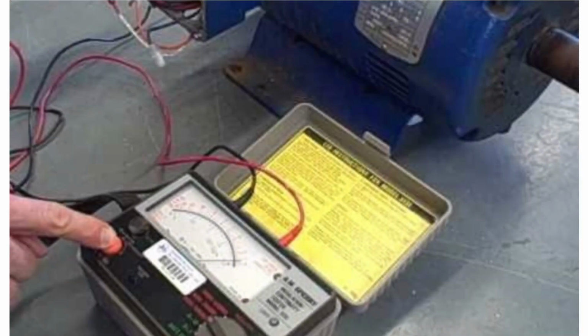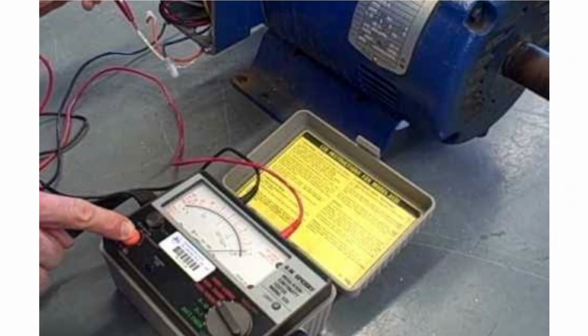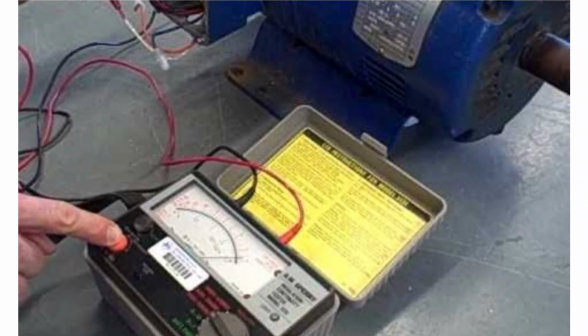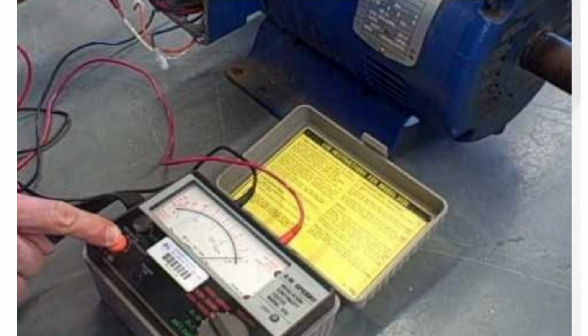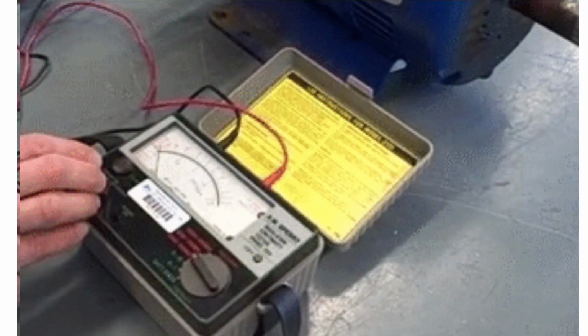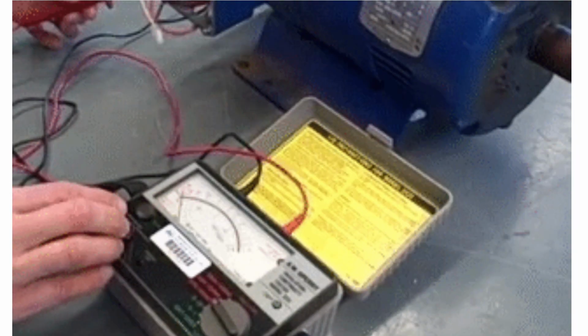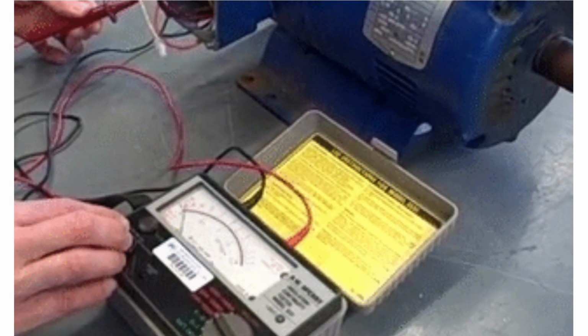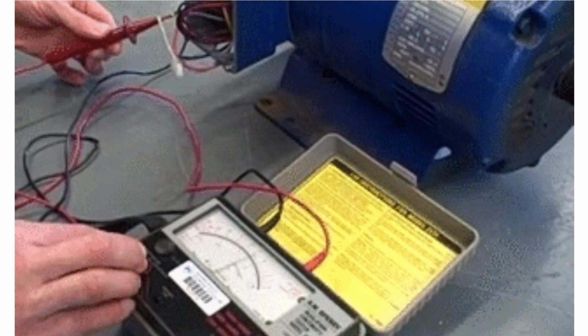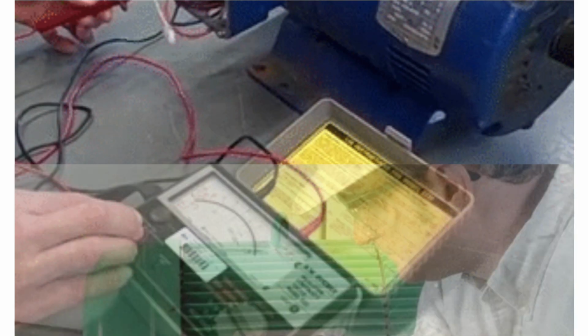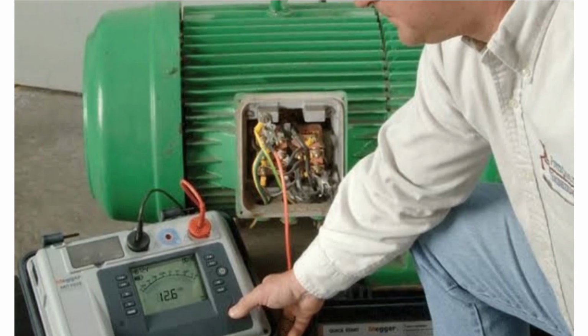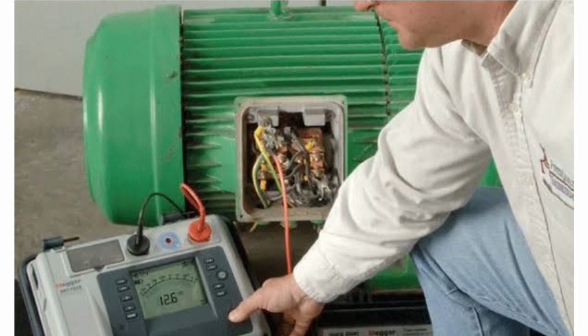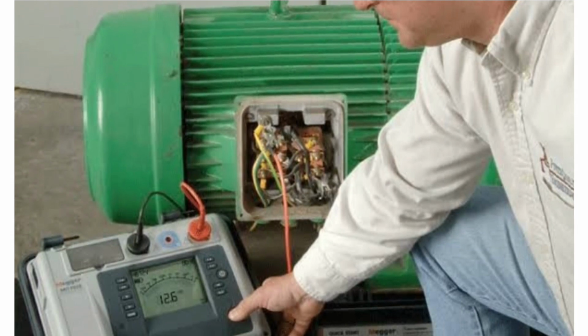To measure a high resistance, apply high voltage up to twice the operating voltage. On a 480 volts motor, for example, apply 1000 V. Perform the readings in megohms. For a motor with a nominal value of 240 to 480 V, it is worth mentioning that different companies have different minimum tolerances for the insulation resistance in the used equipment, ranging from 1 to 10 megohms. The insulation resistance in new equipment should be much higher, from 100 to 200 megohms.